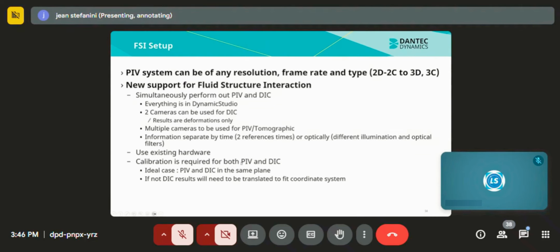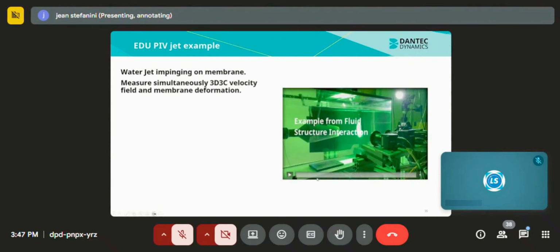So we recently introduced what we call FSI. The PIV system can be any type. It could be 2D, it can be 3D, 3 component, 2 component, whatever you want. And it can measure simultaneously what we call PIV, so velocity, and DIC, which stands for digital image correlation, which is a deformation measurement. We need to use 2 cameras for DIC, and we need to use multiple cameras, 1, 2, or 4, depending on whether you have a 2D PIV or a tomographic. So the same hardware can be used. The ideal case is you have PIV and DIC in the same plane. If not, if you have an orthogonal plane, which is what you will see here, then you need to reconstruct in order to put it in the same plane.